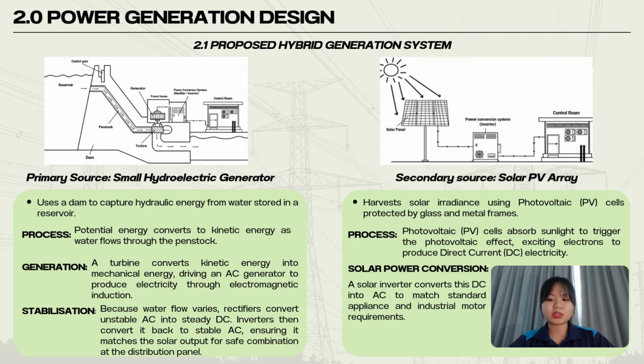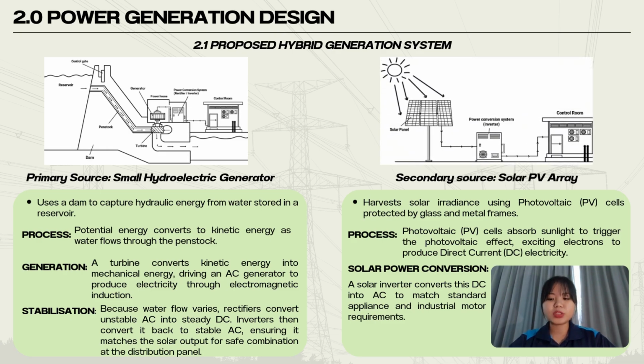The primary source is a small hydroelectric generator which uses a dam to capture hydraulic energy from water stored in a reservoir. The potential energy converts to kinetic energy as the water flows through the penstock. A turbine converts kinetic energy into mechanical energy, driving an AC generator to produce electricity through electromagnetic induction. Because the water flow varies, a rectifier converts unstable AC into steady DC.